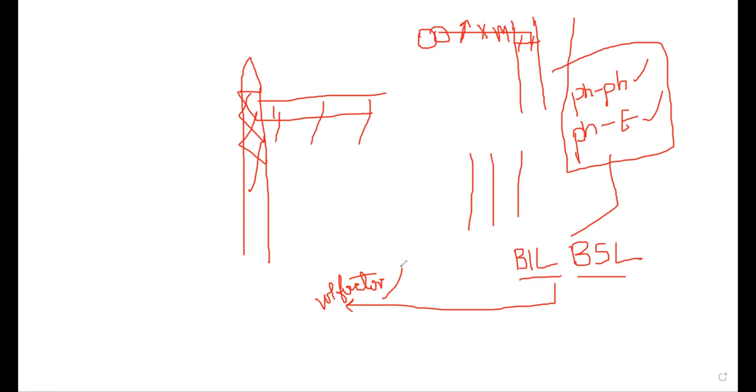I mean less than this or desired ones and the next one is where you are placing the lightning arrestor to attain these values and after getting these BIL and BSL levels, I am calculating the phase to ground and phase to phase clearances.